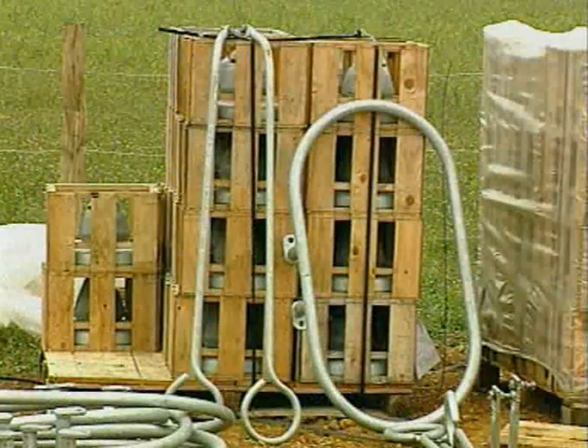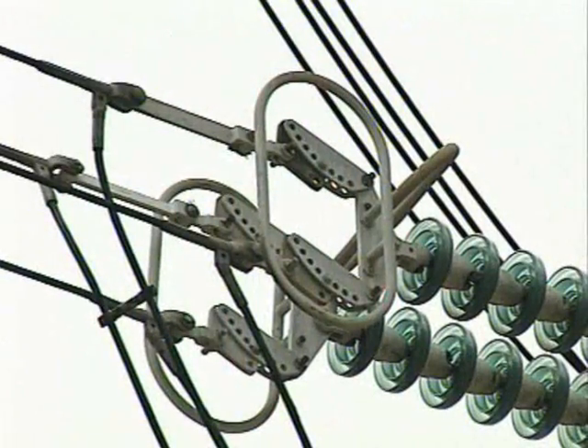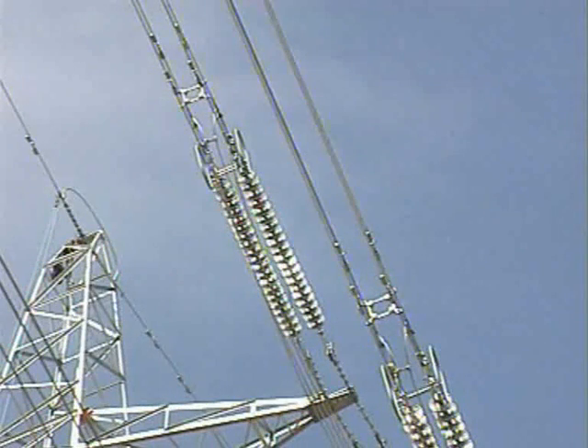To help prevent this, horns are fitted to both the conductor and to the earthed end of the insulators. These serve as spark gaps, which when an abnormal voltage builds up, allow it to harmlessly jump the gap and pass to earth without damaging the insulator.